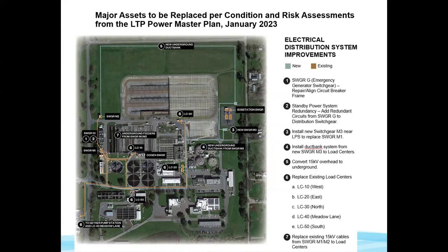There's also additional power supplied to the plant by the cogeneration facility, microgrid batteries, and emergency generators. All loads can be made operational and re-energized by disconnecting the failed power source and closing the circuit breaker at the load centers.